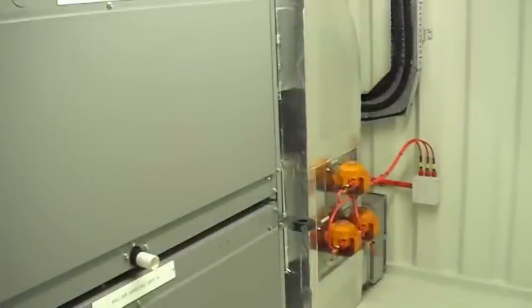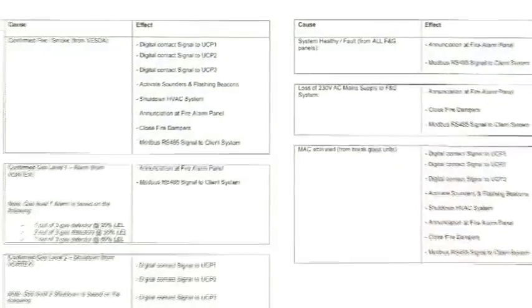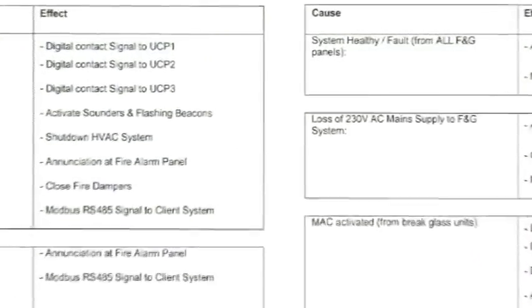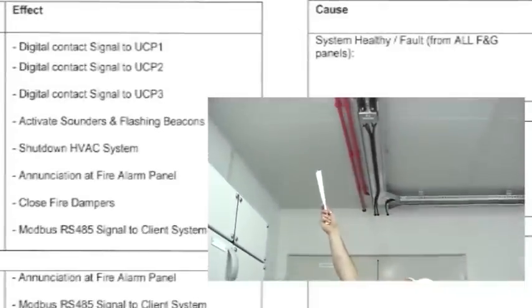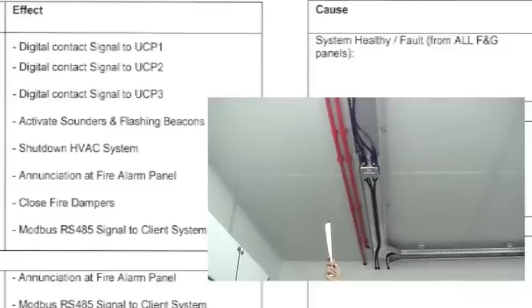3 methane gas detectors provide detection of flammable gases at the HVAC inlet and operate on a 2 out of 3 voting system. A fire and gas cause and effects chart is produced to determine what action is required under a certain condition.